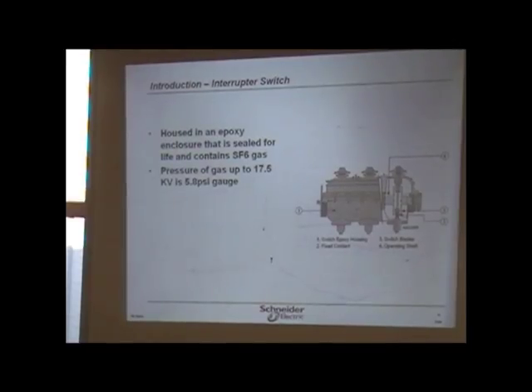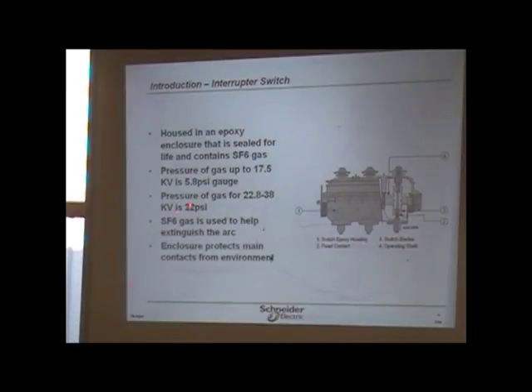This will have high potting values, approximately 2.5 times, on your medium voltage switch here. And even on your low voltage switch here, you've got 480, and you actually don't high pot, but measure to 1,000 or even 5,000. So that way you know for a fact if anything's shorted on there. And those are the different pressures for the different kV. The gas itself is used to extinguish the arc, and it's compressed, so it's pressurized versus a vacuum.